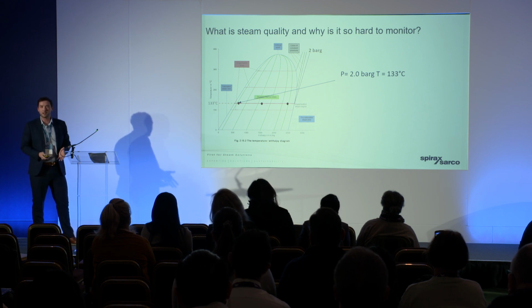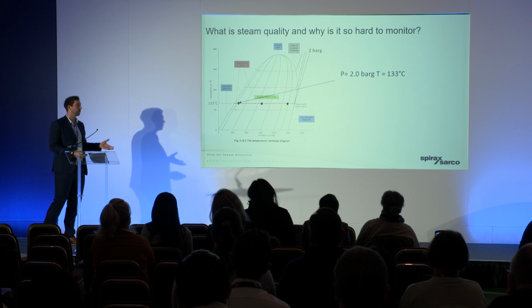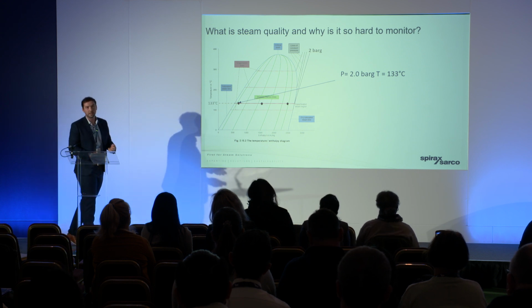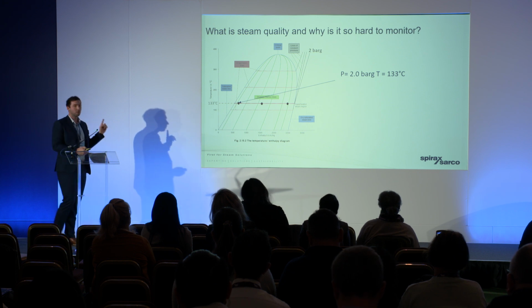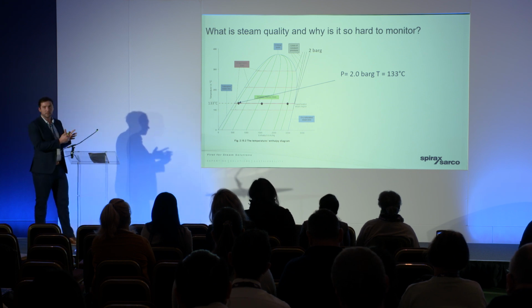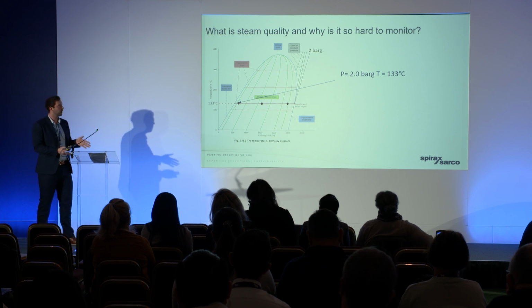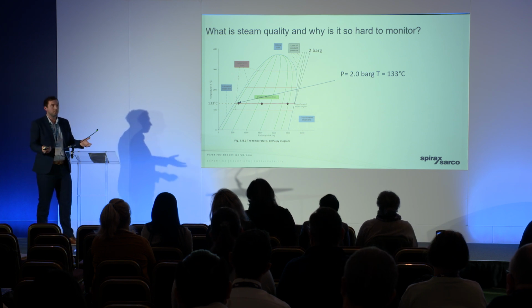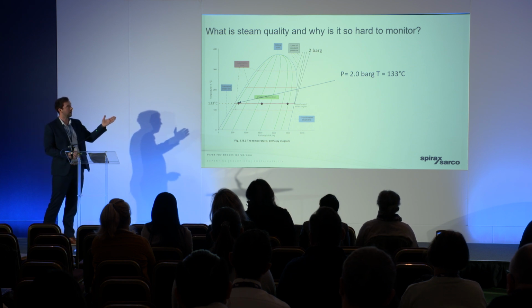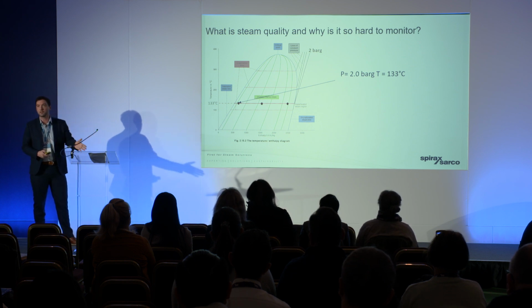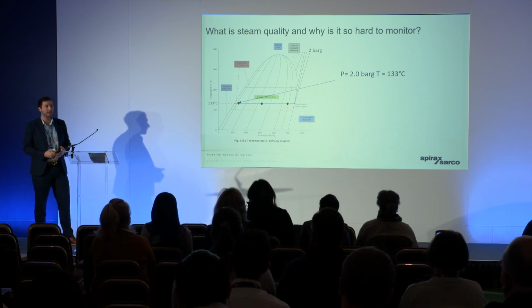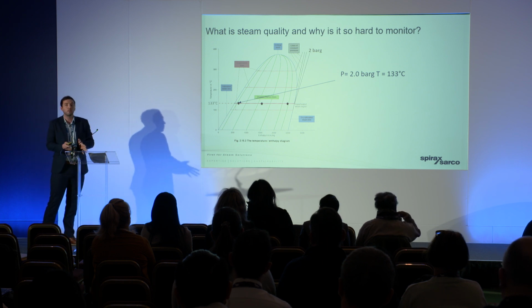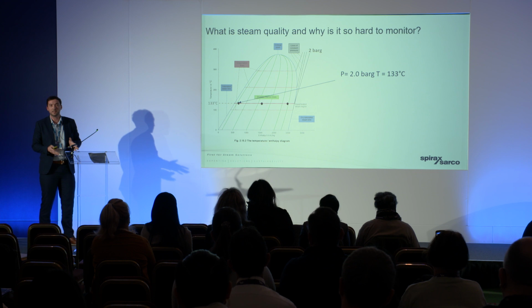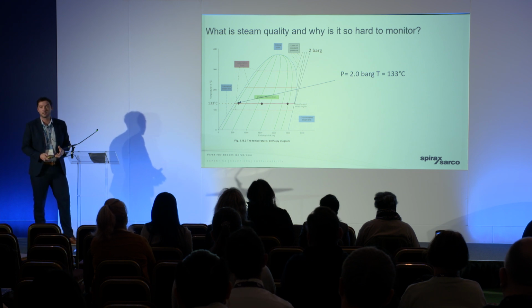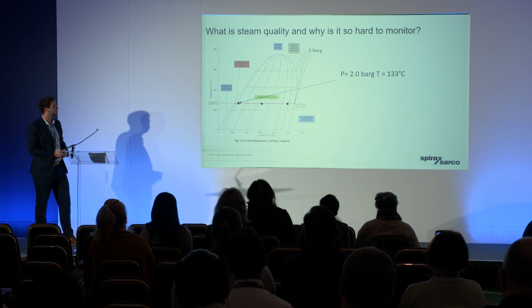It also makes it really hard to monitor. So pressure and temperature, really easy to monitor. Pressure sensor, temperature sensor, really straightforward. But across this line that we're going to go through in a minute, across that transition from being a liquid to a gas, the pressure and temperature doesn't change. So how are we going to monitor it? We could have a pressure and temperature of 2 bar, 133 degrees C, be completely liquid. We could be 100% gas. We just don't know. So when Chris gets on to explain how we validated it, you'll see actually how complex that is and how important knowing the equipment that you're using is actually generating pure steam is very important.